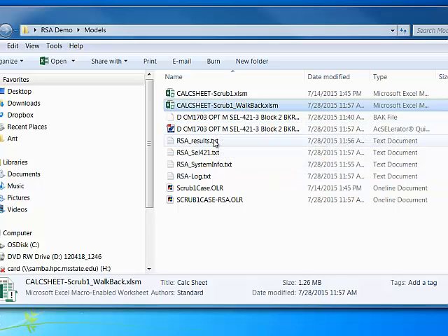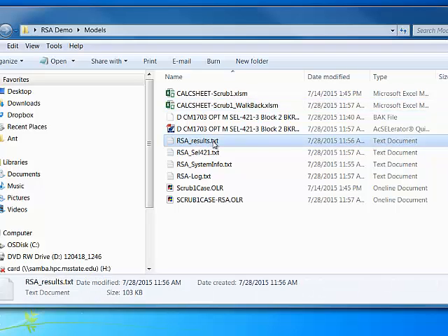You'll see a text file that contains the results of every fault that was run. The results of every fault will not be placed into the calc sheet. The best or worst case one, whatever the program or calc sheet is requiring. Does it need the minimum fault current? And if so, we'll run all the faults and find the minimum and only put that one in the calc sheet. But you do have the record of every fault that you ran for the system.